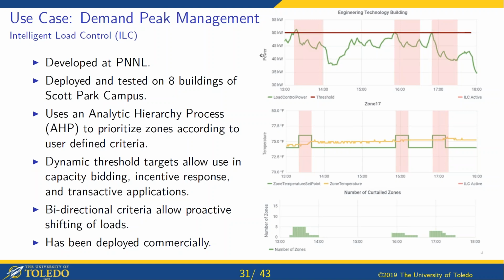We can see these in real time as they're coming in, or look back on them for historical data. This red line is the threshold we set at this point in time, 50 kilowatts. As the power meter in the building reaches that, it's quickly brought back underneath it, coming up a few more times, each time kept underneath it by choosing some number of zones.